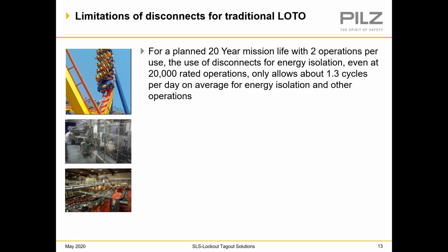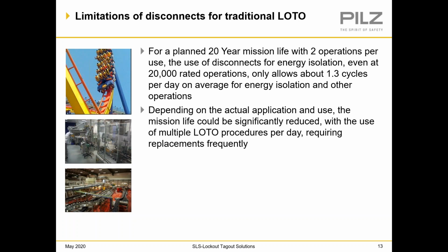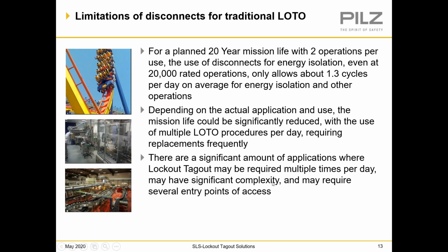So over 20 years, you're averaging 1.3 cycles per day if you're going to use this for lockout. And that's not very much. So depending on the actual application and use, the mission life could be significantly reduced with the use of multiple lockout procedures per day, requiring replacements frequently. So there are a significant amount of applications where lockout, tagout may be required multiple times per day, may have significant complexity, and may require several entry points of access.